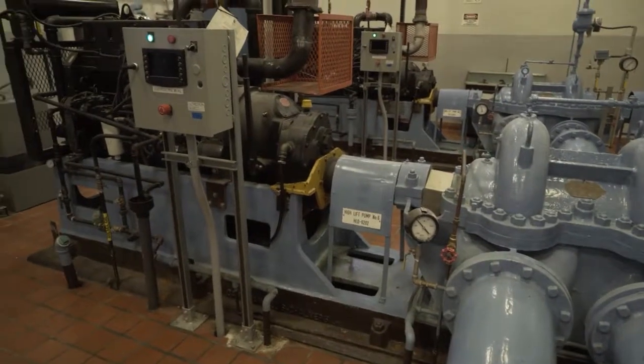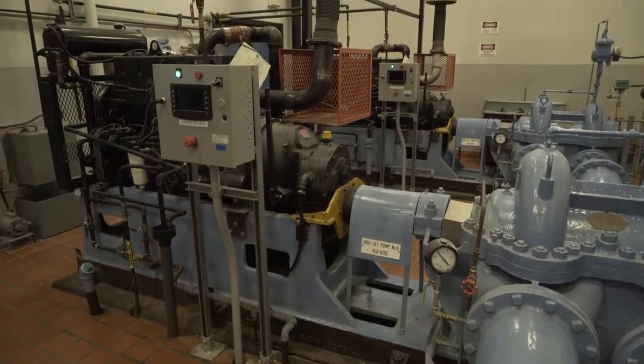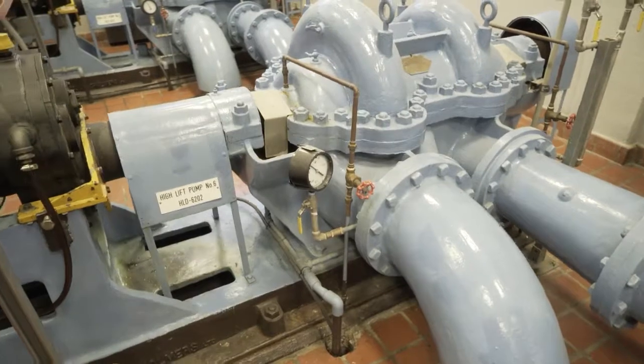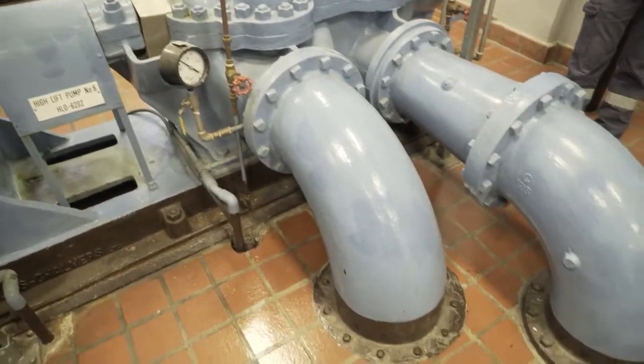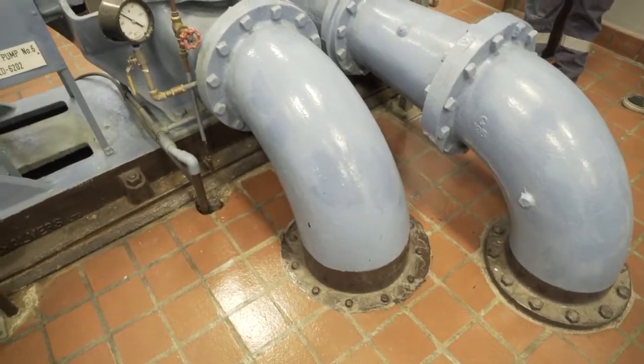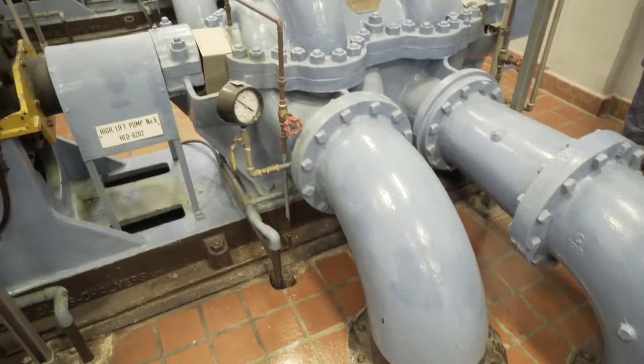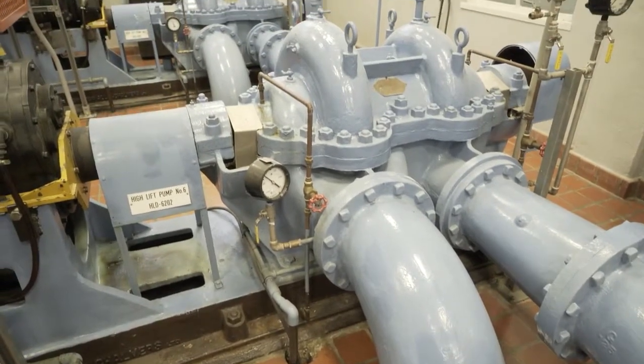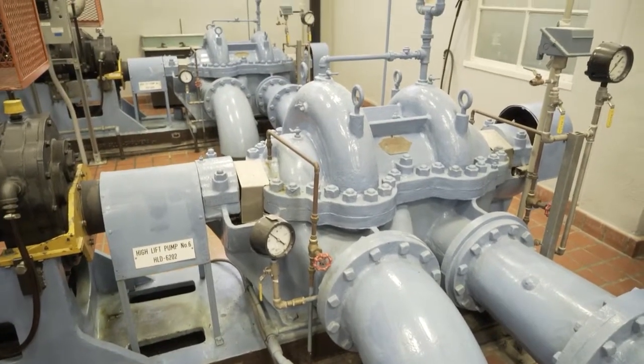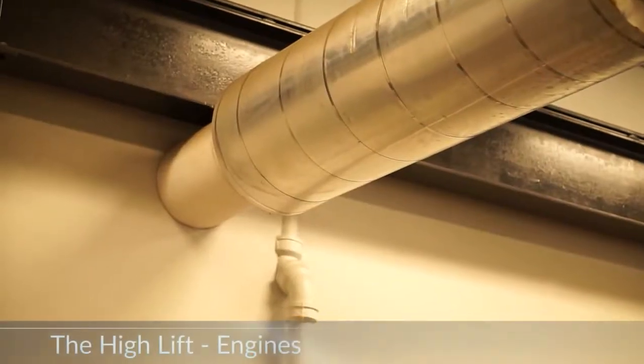Both high and low lift pumps are double suction. That means the intake port, the suction, splits in two so the flow goes into the impeller from both sides. By balancing the momentum of the flow, this eliminates the thrust force that would be on the shaft of a single suction pump. Lower stresses and no need for big thrust bearings.